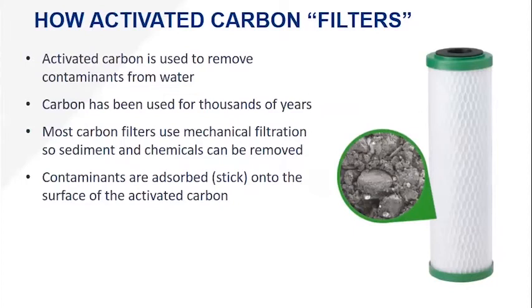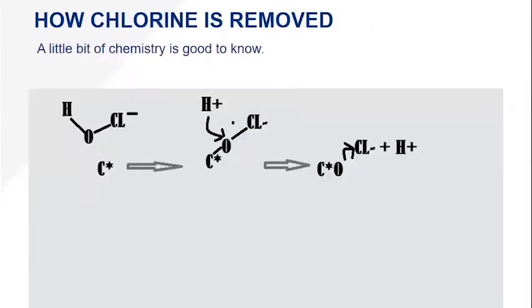There is a very different dynamic between dirt loading and chemical extraction with activated carbon, and that's critical to understand. We'd rather use a pre-filter to manage our dirt load than waste our activated carbon filters managing dirt.